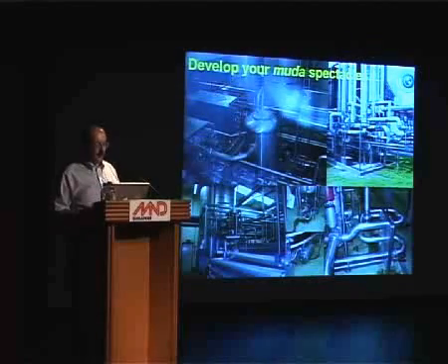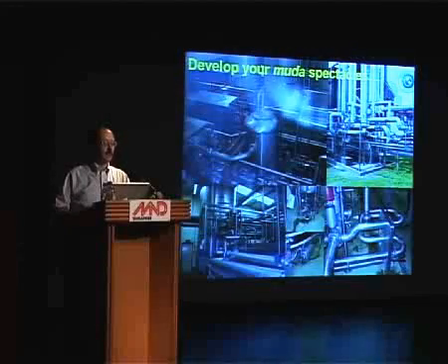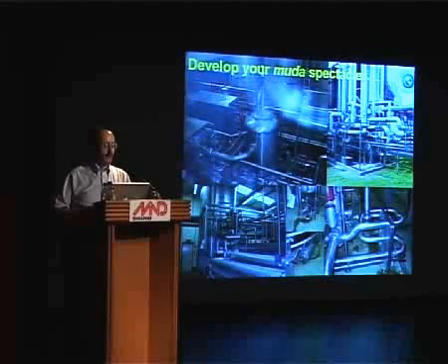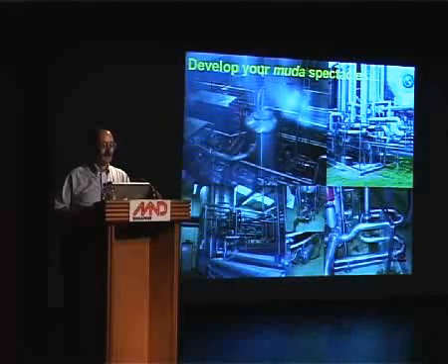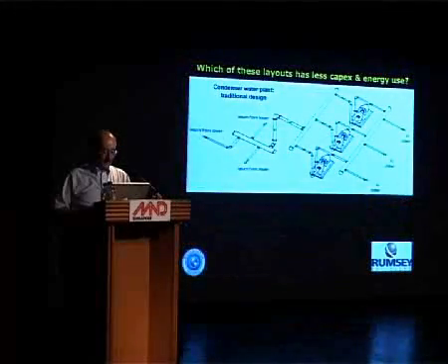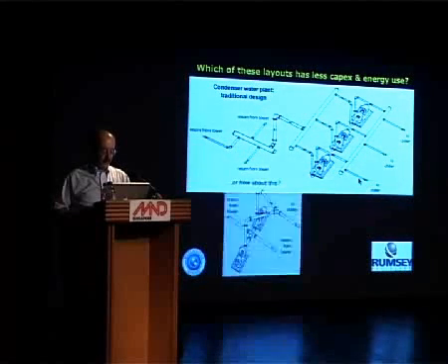The best example I know is actually from a brilliant engineer at Stone & Webster who was doing a bit of an ethylene plant, and by untangling the layout, he was able to reduce the number of elbows from 29 to 3, and these were half-meter diameter stainless elbows. So he was a very happy camper. Here's a common error. I'll bet many of us have designed piping runs like this to bring back water from a cooling tower to a chiller. How about doing it this way?